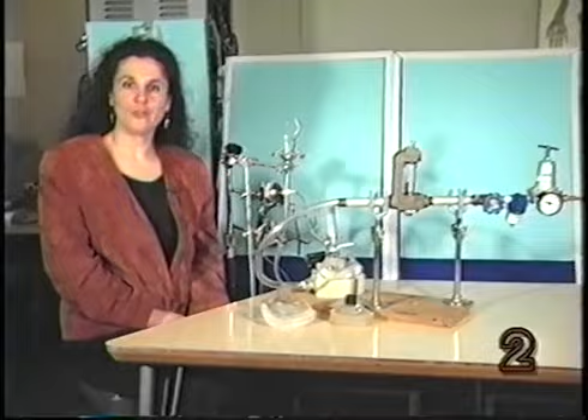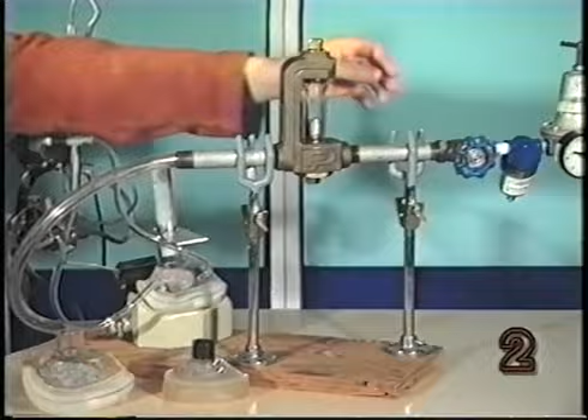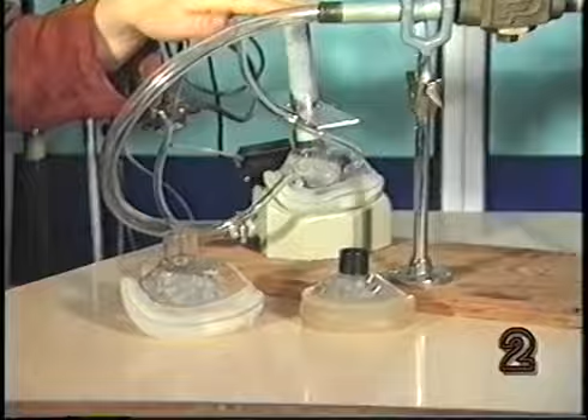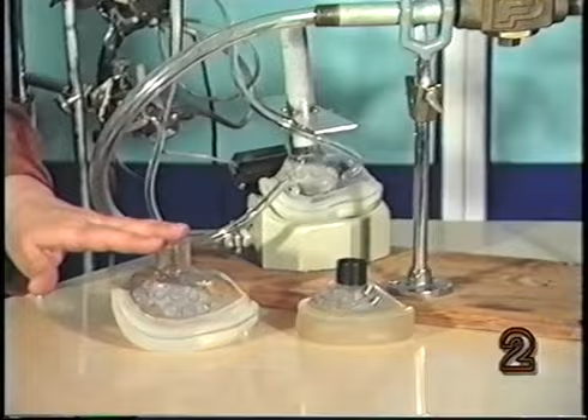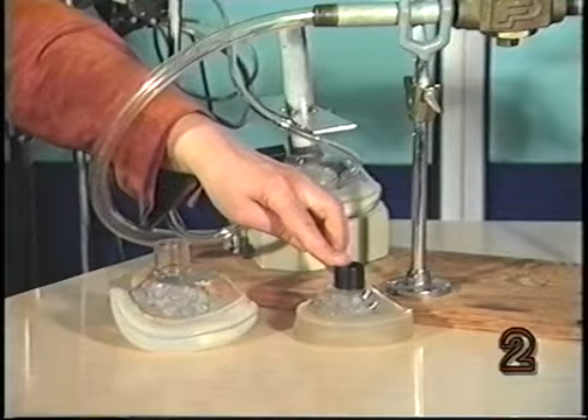Now I'm going to demonstrate how we calibrate for airflow, air pressure, and air volume. To calibrate for the airflow, we place the pneumotachograph on the mold. While using a device called a rotometer to indicate the flow moving through the mask transducer system, we record this signal and use it for later reference. We calibrate for airflow for each mask size that we use. So this is the medium-sized mask, and this is the one that's used for adult females and teenagers. We use the large size mask for adult males, and this is the small size mask that's used for the younger children.